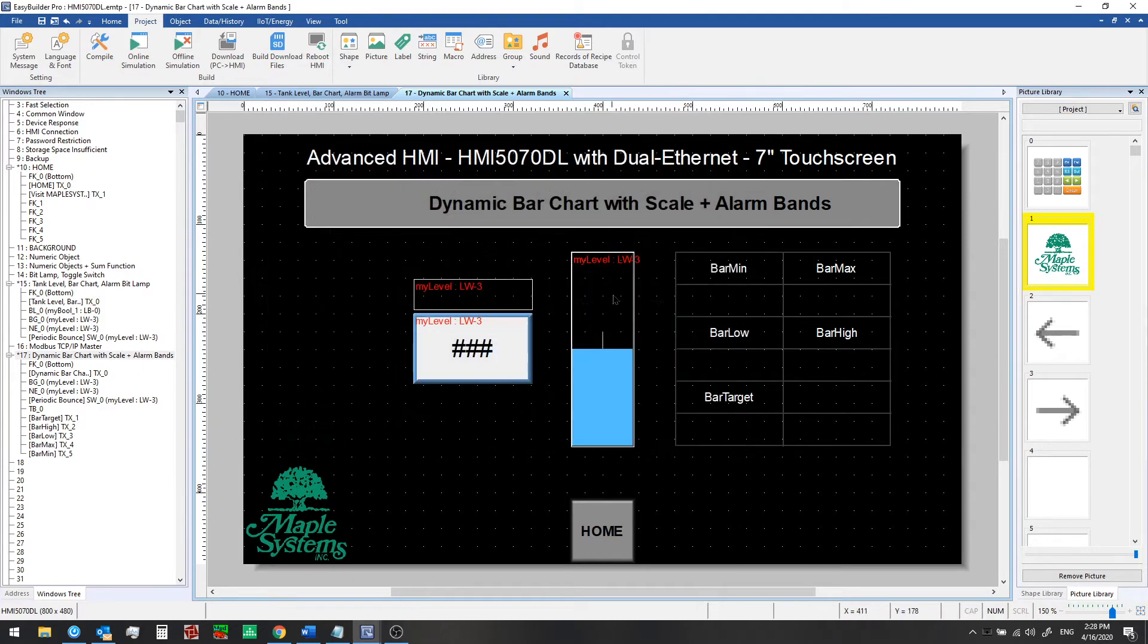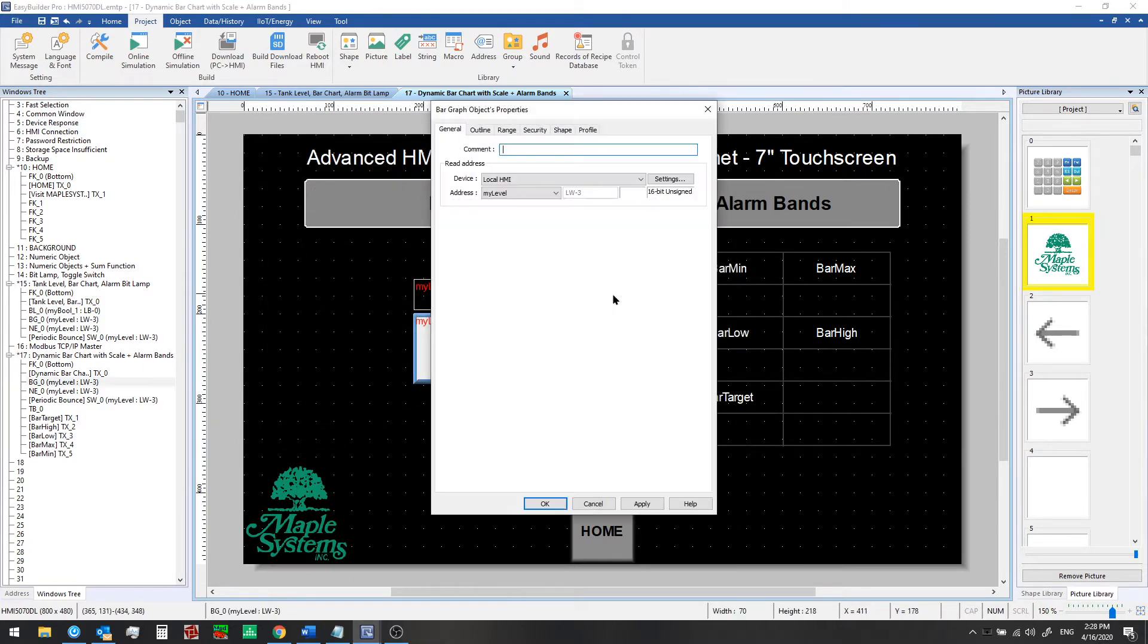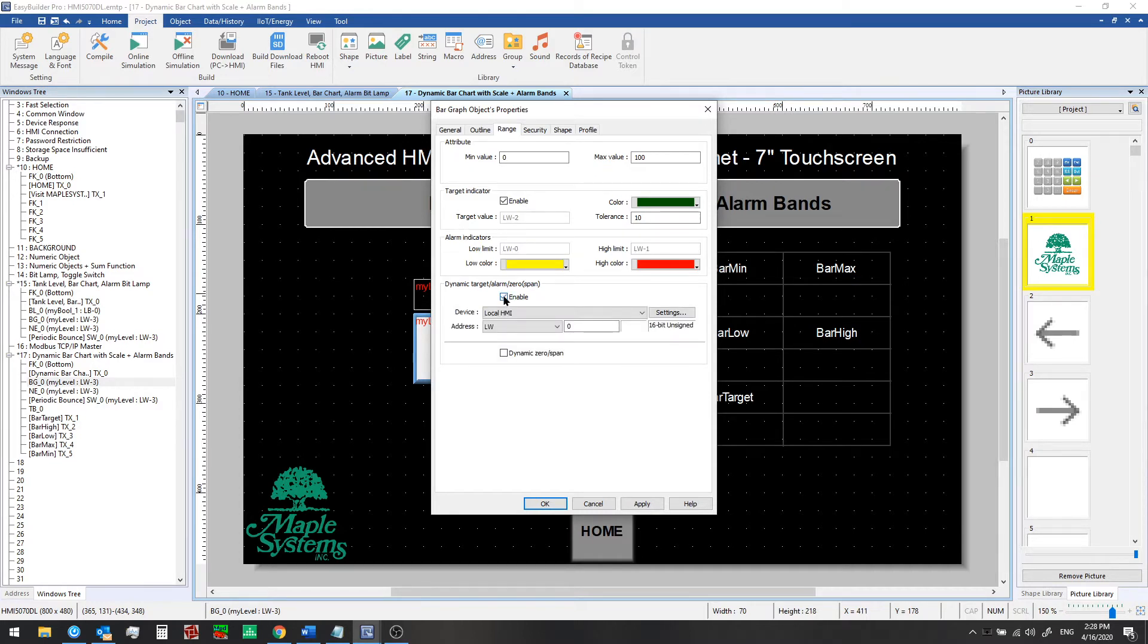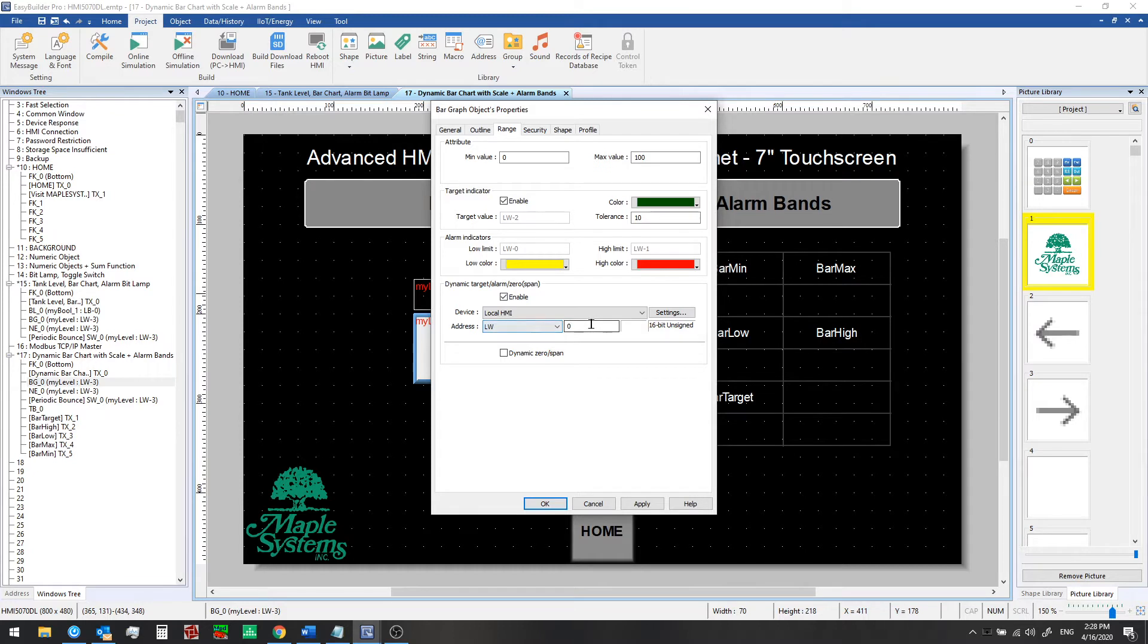We go back to the range tab. First we're going to enable the dynamic target alarm setting here. When we first check this box it will start us off at local word 0 as a read address and it will set up the consecutive registers - two of them, local word 1 and 2 - as high limit and target value respectively.